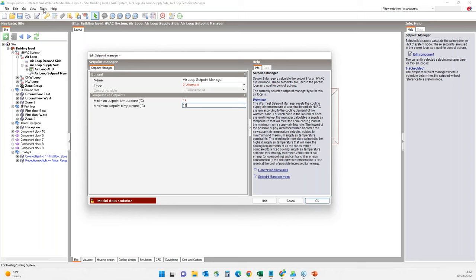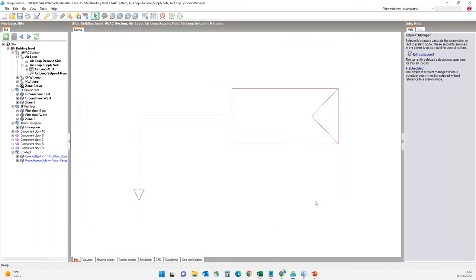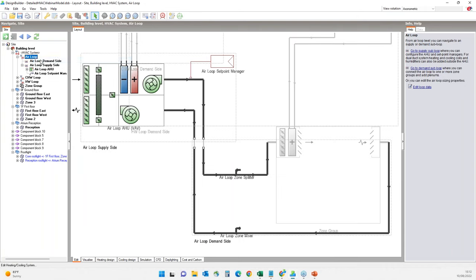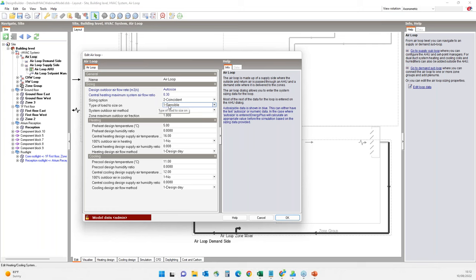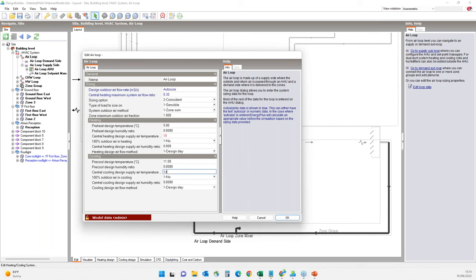On the air loop edit dialog we have all the sizing details for the air loop, such as type of load to size on. In this case it is sensible load because this is an all-air system and we must meet the entire heating, cooling, and ventilation needs of the building. In line with our setpoint manager settings, we also need to correct the coil sizing temperatures: design supply temperature for heating needs to be 18 degrees and for cooling 14 degrees.